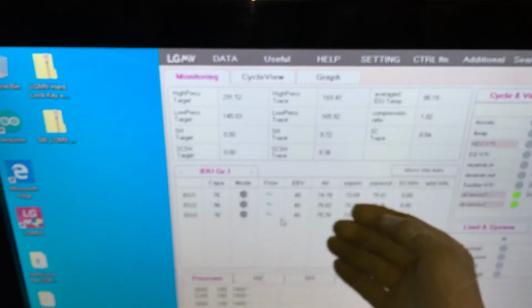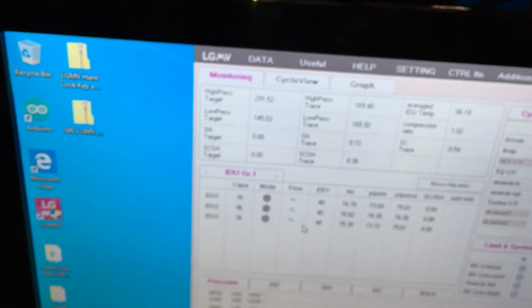Or you see one wide open and it was at, you know, like 800 counts and all the rest of them on 200 systems are at 400 counts, but one was at 800. You go, okay, why is that one air handler just feeding a ton of refrigerant all the time trying to catch up, but it never catches up, and yet it did not set an alarm code? So that's the purpose for this. This is just a step above and beyond anything that most anybody else does for us.